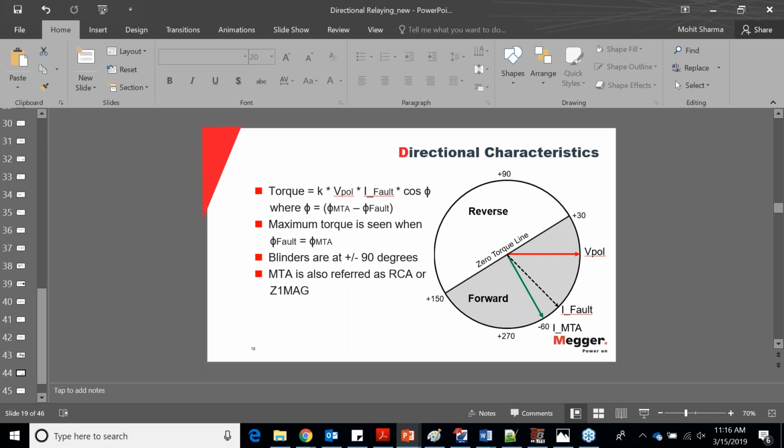Adding to Mohit's answer: 32GF and 32QF are direction elements. It's like a ground, zero sequence and negative sequence detection in the SEL relays. It's specific to one particular relay. They use a negative sequence element and a zero sequence element to start measuring the 67 functionality. Either can be used, and it's true, yes, 32 is very sensitive. It has to be configured and set properly.